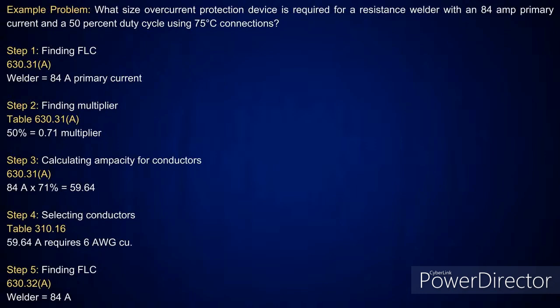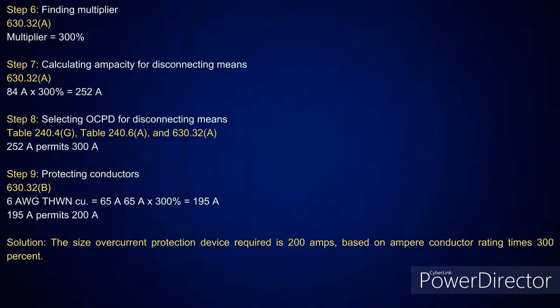The only difference between these two, when I look at 630.32A and you're doing a resistance welder, is that you're going to take it at 300% instead of 200%. So I'm going to take the 84 amps at 300%, and that's going to give me 252 amps. Now we're going to show you, looking at this overcurrent protection device, I'm going to go up to the next standard size just to show you here. So here's 300 amps. Now, if I look at protecting the conductors, if I took that 65 amps at 300%, that gives me 195 amps.